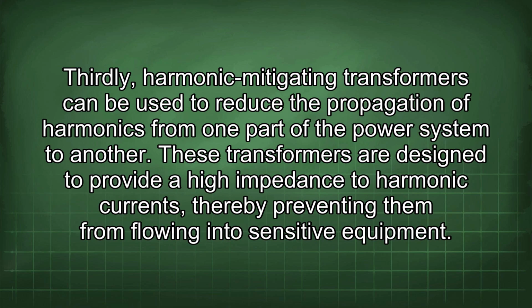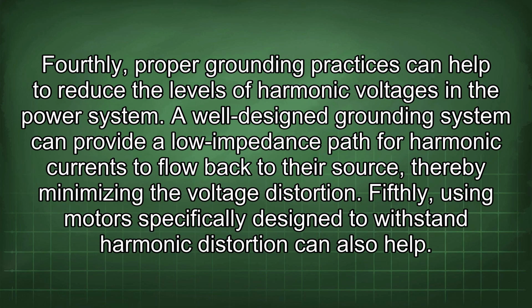Thirdly, harmonic mitigating transformers can be used to reduce the propagation of harmonics from one part of the power system to another. These transformers are designed to provide a high impedance to harmonic currents, thereby preventing them from flowing into sensitive equipment. Fourthly, proper grounding practices can help to reduce the levels of harmonic voltages in the power system. A well-designed grounding system can provide a low impedance path for harmonic currents to flow back to their source, thereby minimizing the voltage distortion. Fifthly, using motors specifically designed to withstand harmonic distortion can also help.